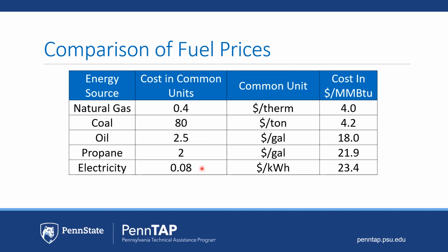A BTU is a basic unit for heat. That is why we have this over here. And you can see that although electricity is 8 cents per kilowatt hour, it is actually $23.40 per MMBTU to burn electricity for 1 hour. And natural gas comes to $4, coal comes to $4, oil is 18, and propane is 21, nearly $22 to burn. This is your apples to apples comparison.